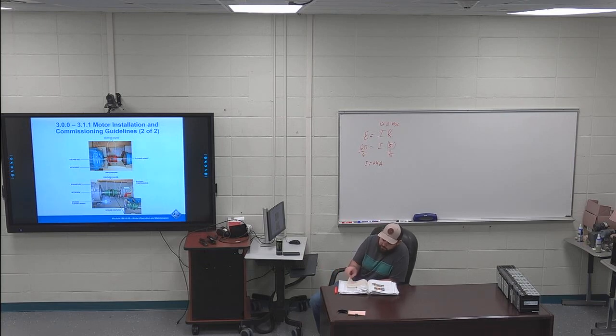I don't have anything else on page 27, but if you're going into page 28, I have a couple of the bullet points coming from the first time startup. The bullet point on page 28 in the bottom left is highlighted: apply power and momentarily bump or start the motor to verify correct rotation. If wrong, again, lock out and tag out the motor and switch two phases, then bump the motor again to check. So this is a common way of testing which way the motor is going to turn. So you hook it up, turn the power on and off as quickly as you can, and you can see which way that motor is going to turn. And if it has to be switched, you can switch phases or switch two of the legs going out there.